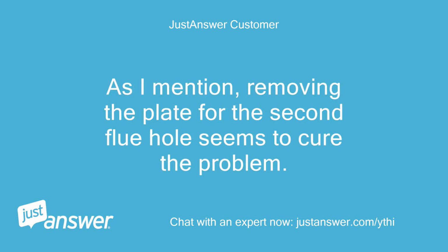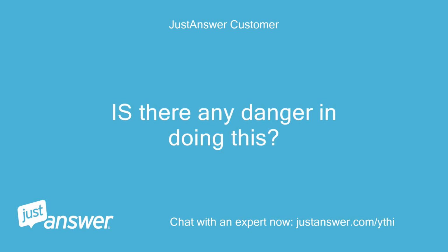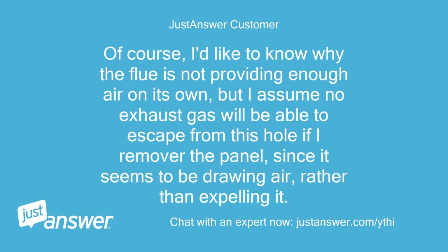As I mentioned, removing the plate for the second flue hole seems to cure the problem. Is there any danger in doing this? Of course, I'd like to know why the flue is not providing enough air on its own, but I assume no exhaust gas will be able to escape from this hole if I remove the panel, since it seems to be drawing air, rather than expelling it.